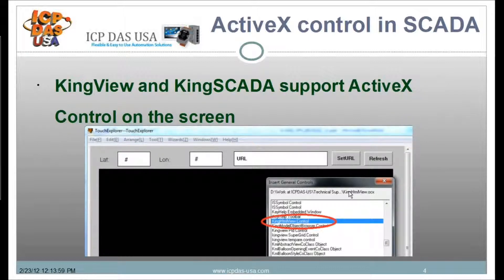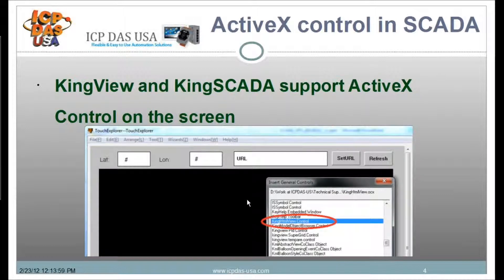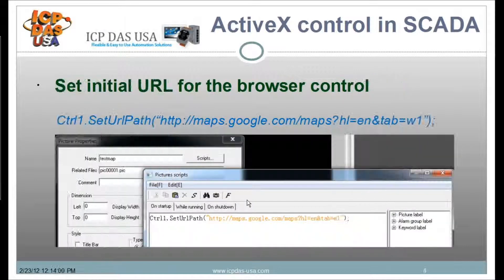Once you're in KingView and KingScada, and once you have the ActiveX control installed, you simply insert an ActiveX control element into your Touch Explorer. Then you set up the initial URL for the browser control within the picture property windows, and this is done with a script — I'll show you how to do that as well.